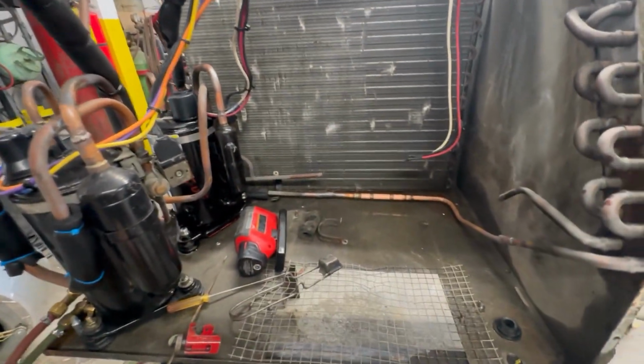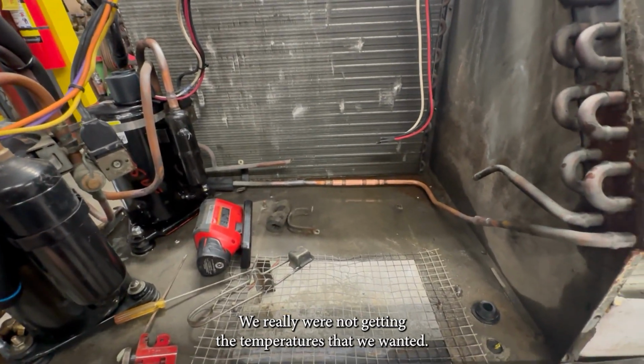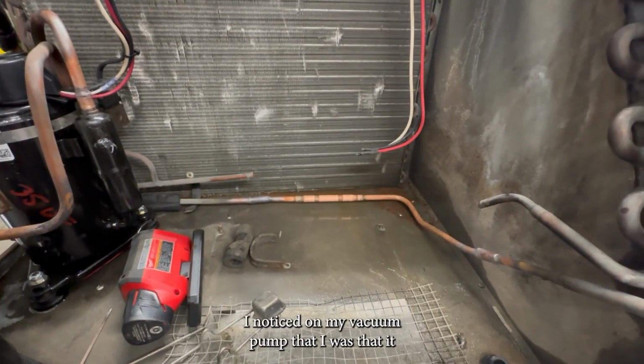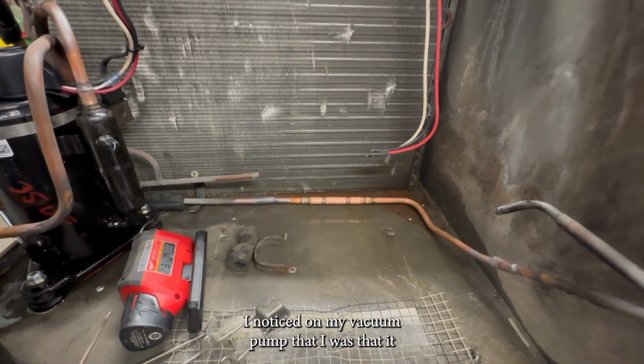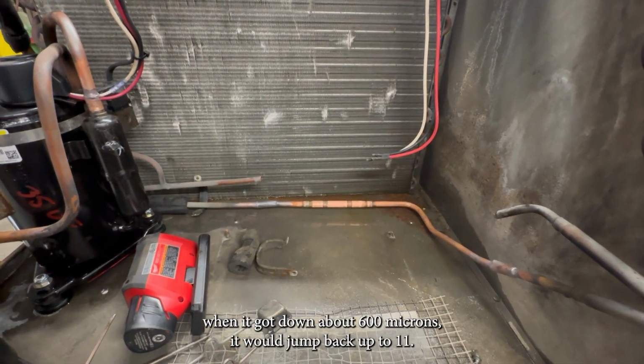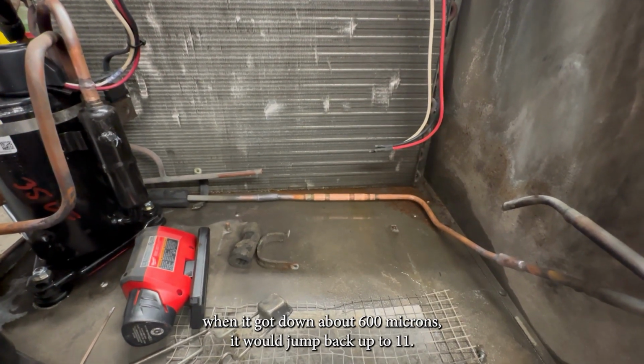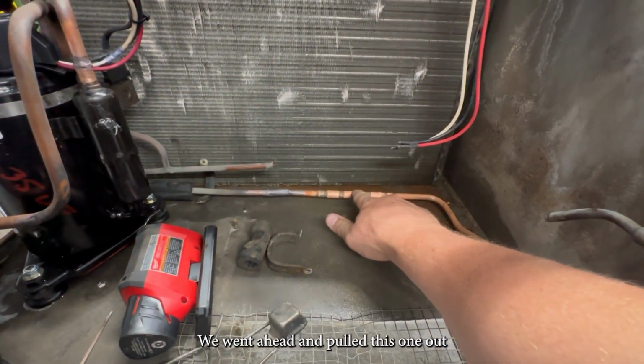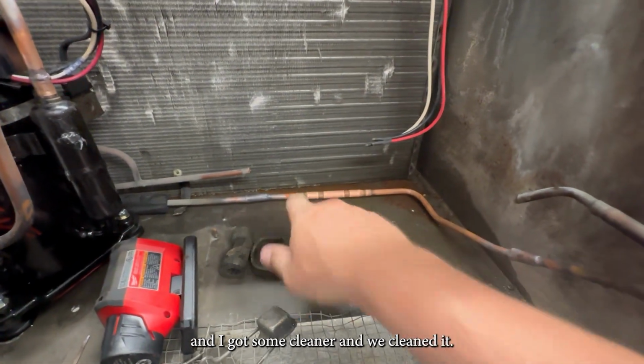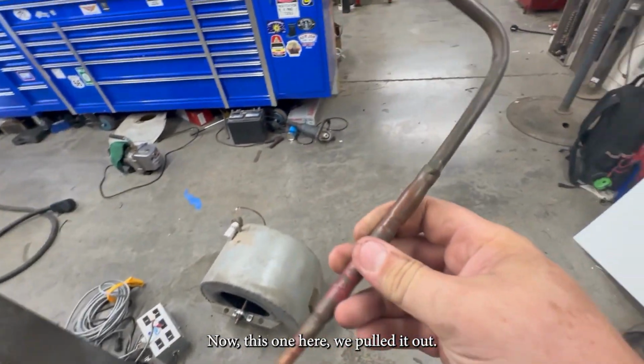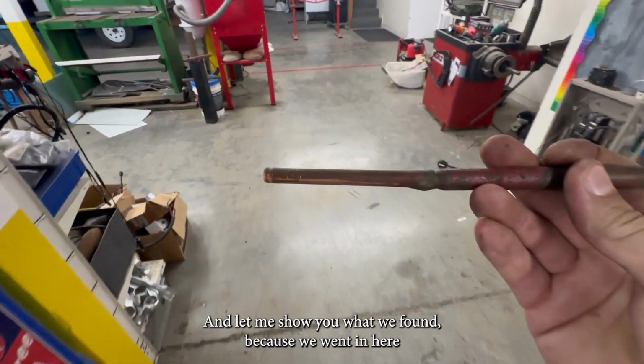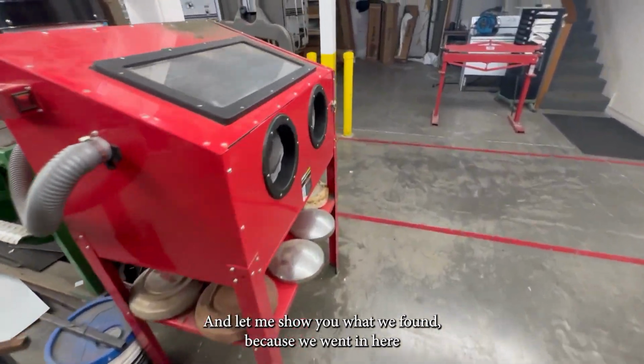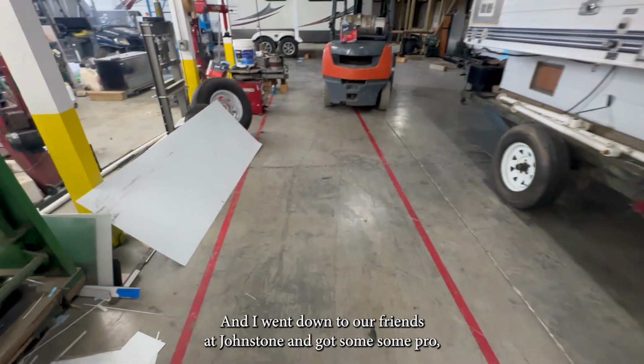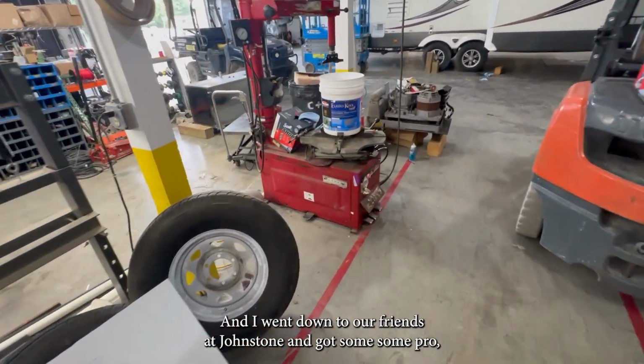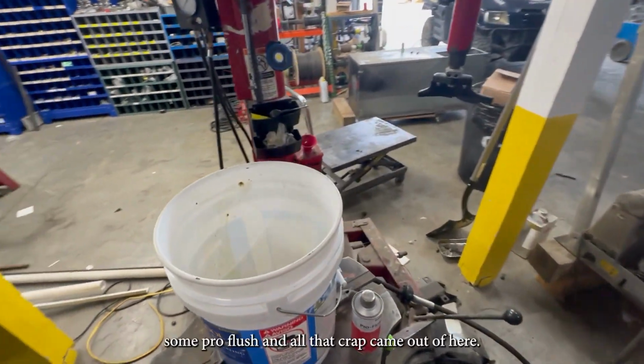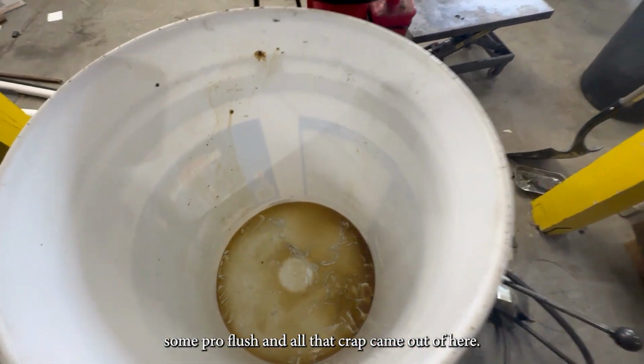We ran it yesterday, and we really weren't getting the temperatures that we wanted. I noticed on my vacuum pump that when it got down to about 600 microns, it would jump back up to 11. We went ahead and pulled this one out and got some cleaner and cleaned it. Now this one here, we pulled it out, and let me show you what we found - we went in here and started cleaning on this thing, and I went down to our friends at Johnstone and got some Pro Flush, and all that crap came out of here.